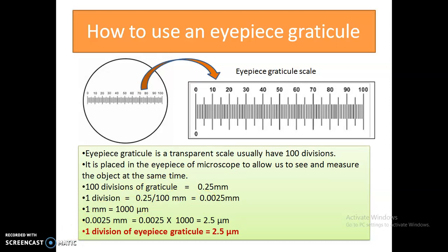The images we observe through the microscope will be very minute, and the correct unit to measure them is the micrometer. So we need to convert this value from millimeters into micrometers. Since one millimeter equals 1000 micrometers, multiplying 0.0025 by 1000 gives us 2.5 micrometers. Therefore, one division of this eyepiece graticule is equal to 2.5 micrometers.